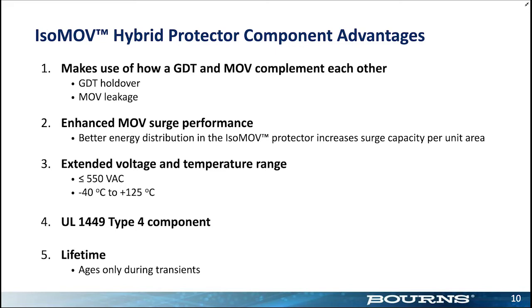That's called GDT holdover, the idea that the GDT stays on even though the surge has gone away. So the MOV solves the GDT holdover problem. And as I said before, the GDT solves the leakage problem with MOVs, right? A GDT is a gap. There's no leakage. And so each one overcomes the deficiencies of the other.